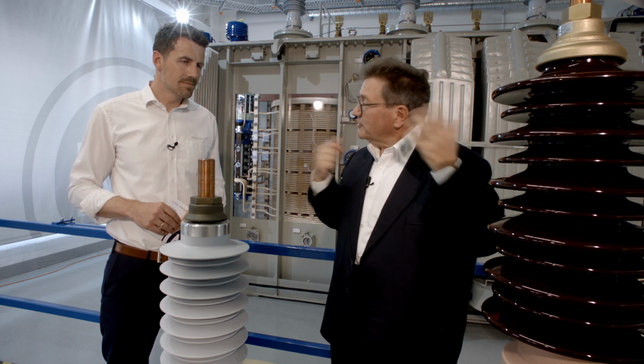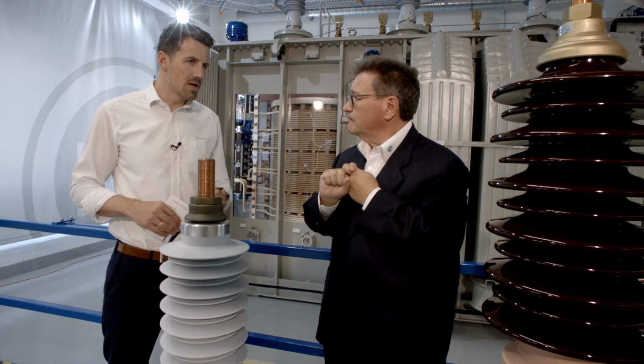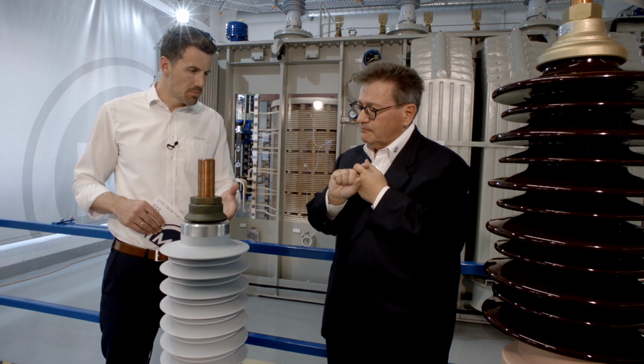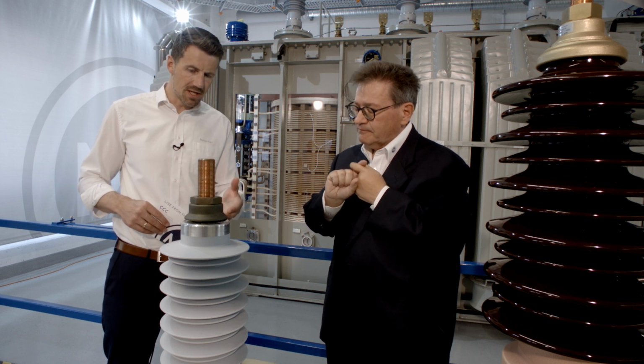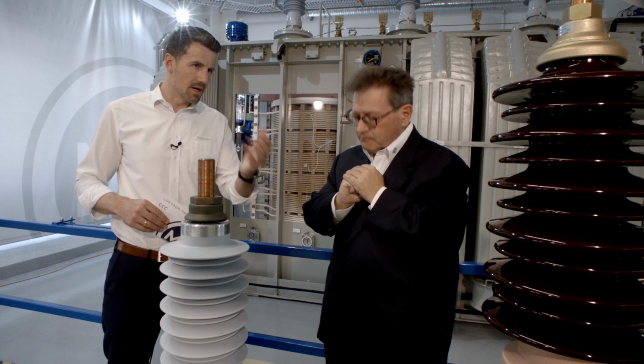And an electrical flashover combined with the oil insulation from the transformer and the oxygen of the air, you get fire. You have to know, from a statistical analysis done by Cigre, one third of transformer fires are caused by failure of a bushing. When I say failure, I mean breaking of the bushing. Okay, thank you, Tullio. Fully understand. That brings me to the point why polymeric bushings, here we see the SBC type from CEDASPE, have clear benefits compared to the porcelain ones here.